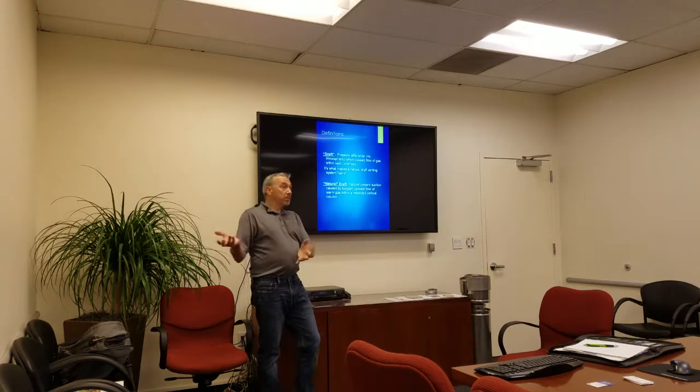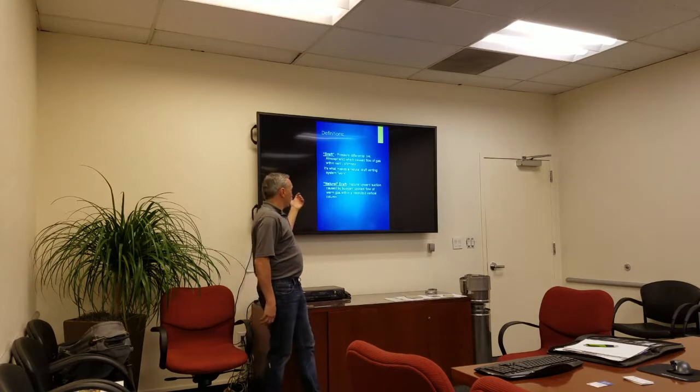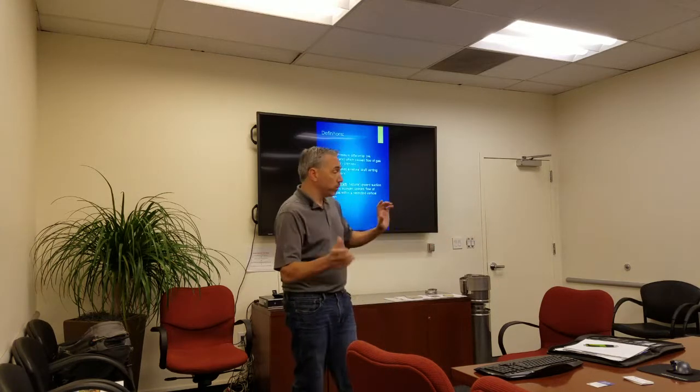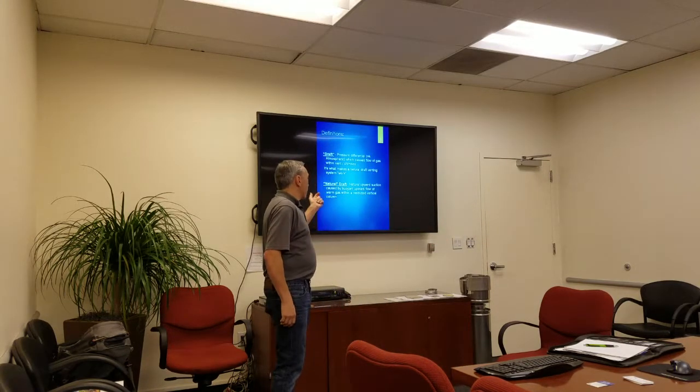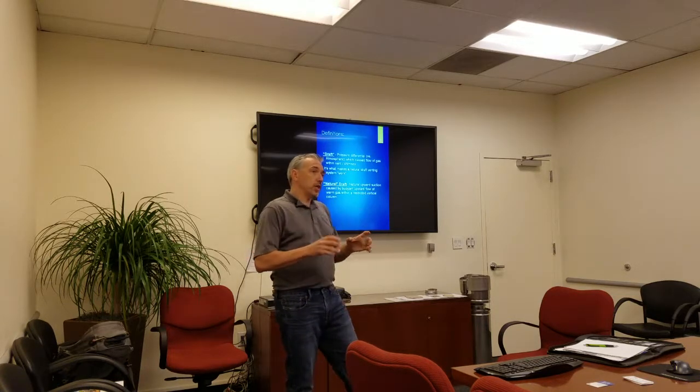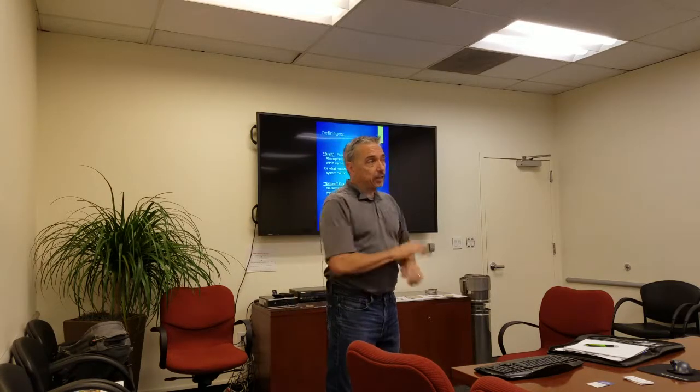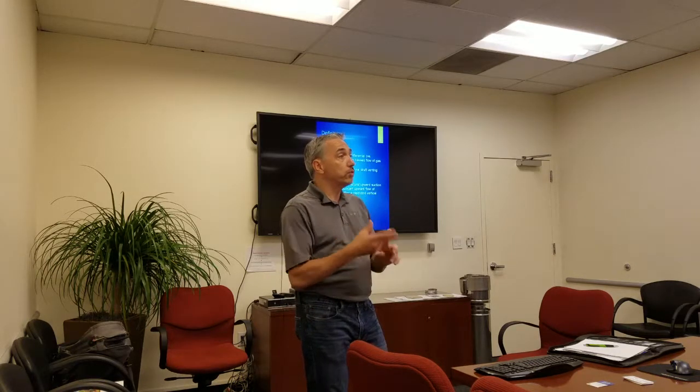Draft is the chimney effect — simply put, that's what draft is. Natural draft relies solely on the heat coming off of the appliance. In a natural draft appliance, it'll be a category one vent and you would use type B vent. With the increase in efficiency, 83% efficiency is the absolute maximum you can achieve on a natural draft boiler. That 17% has to be left over to make sure the flue system works.